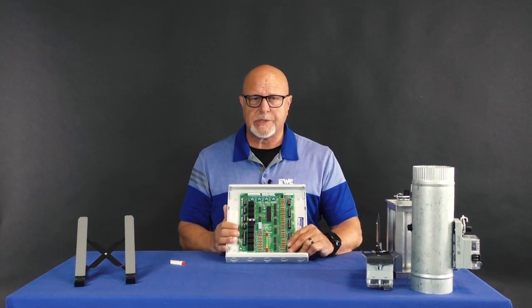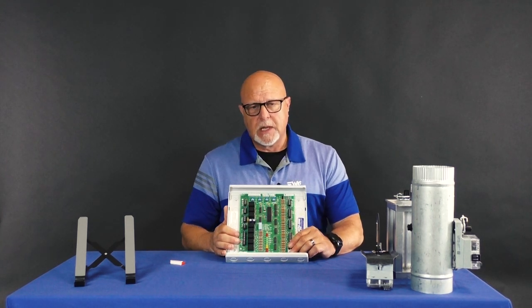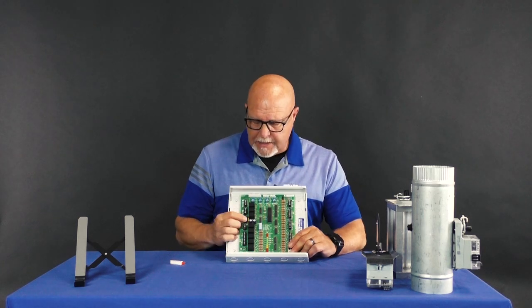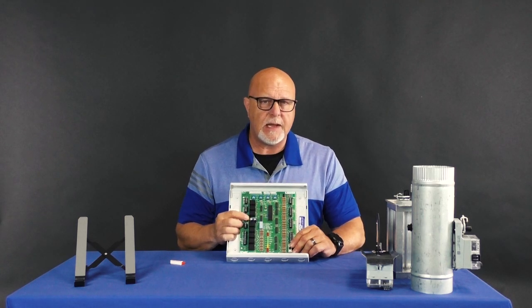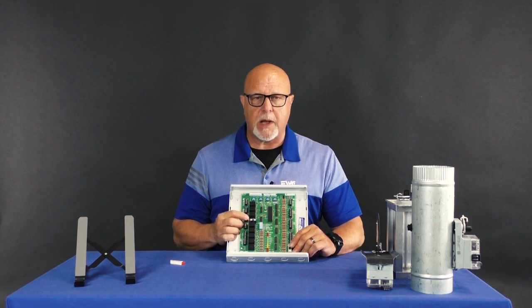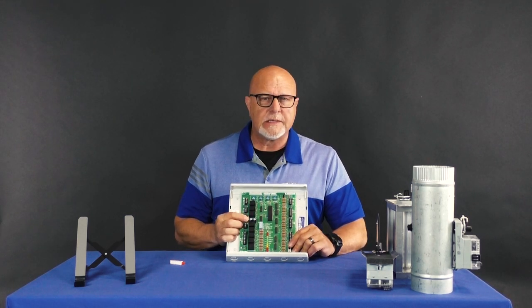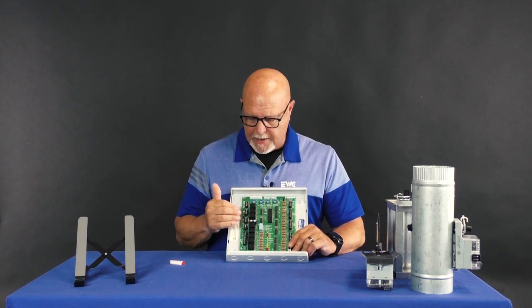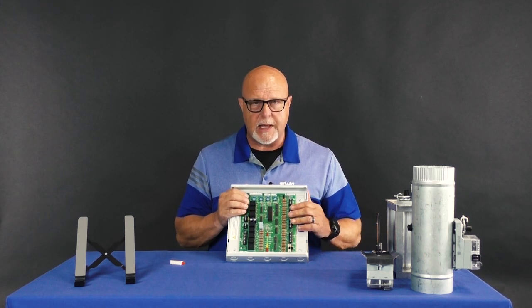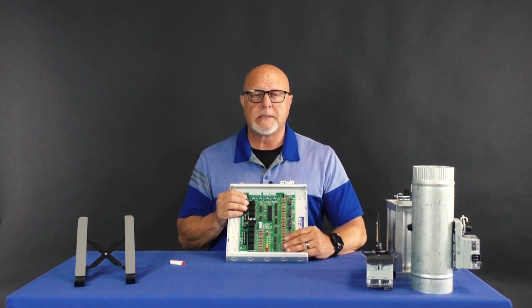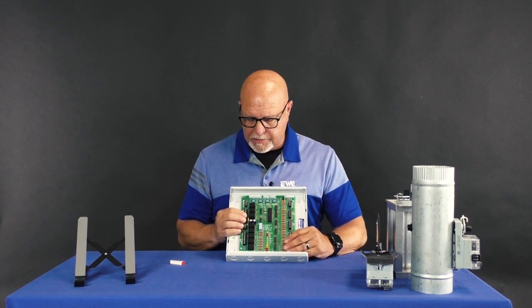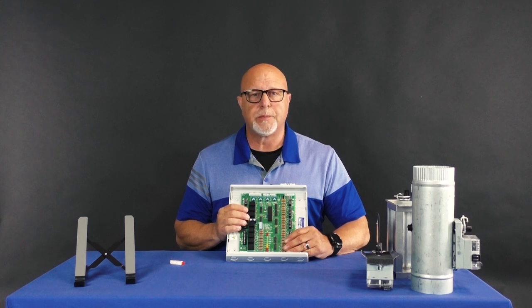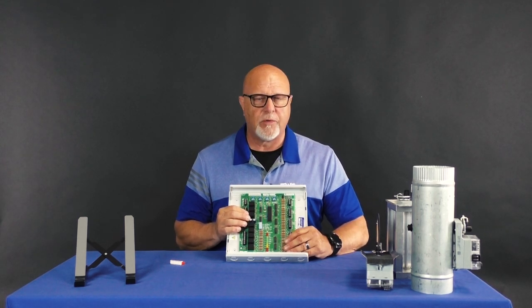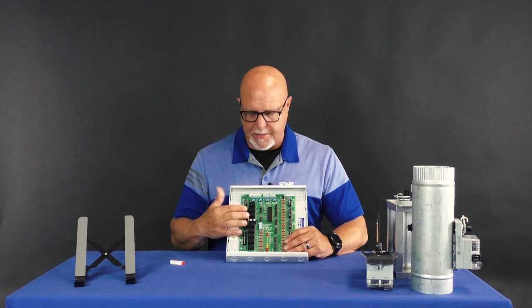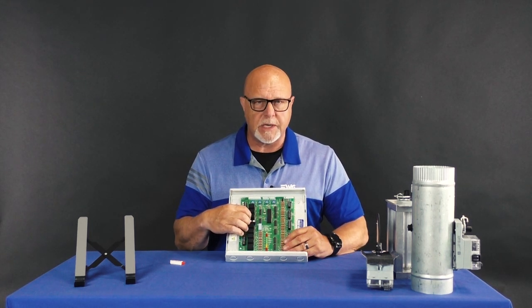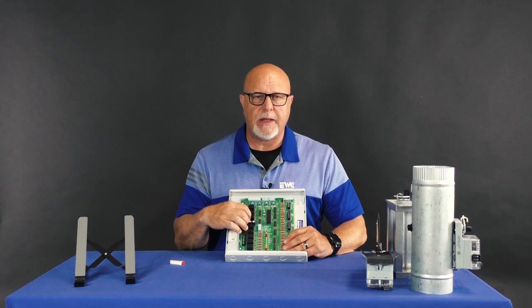One of the other key features that we have employed with the BM Plus line, and for that matter all of our zone boards, is our protection system. This is a thermal circuit breaker, a little poly fuse. In the event that there is a short in your system between dampers and our board, or thermostats and our board, it will recognize that abnormal power supply, and it will shut down to protect itself. If the short is left there for a small amount of time, this polyfuse will become warm to the touch. And that's your first indication that something is wrong.